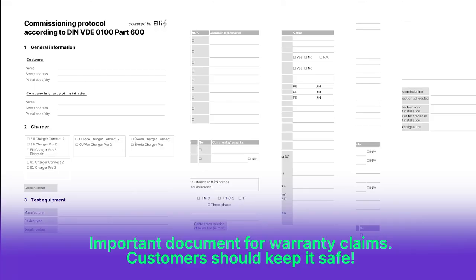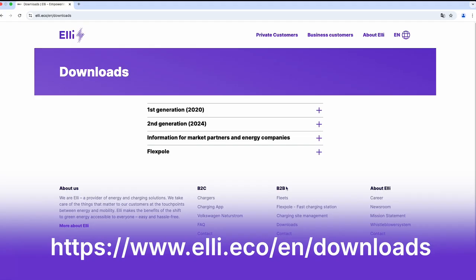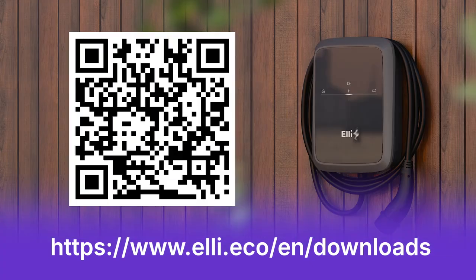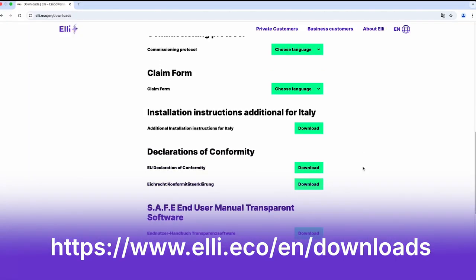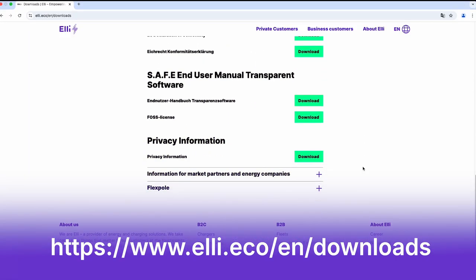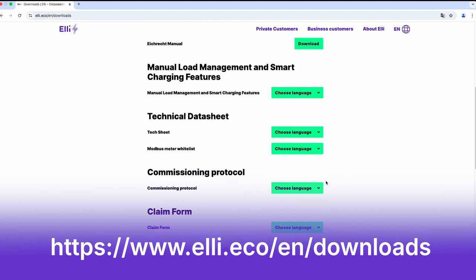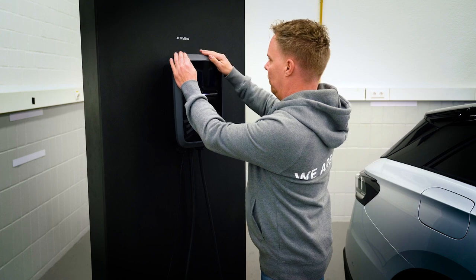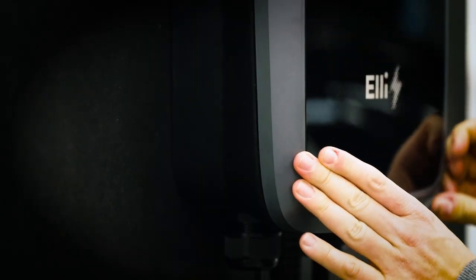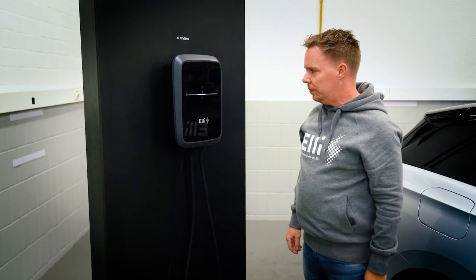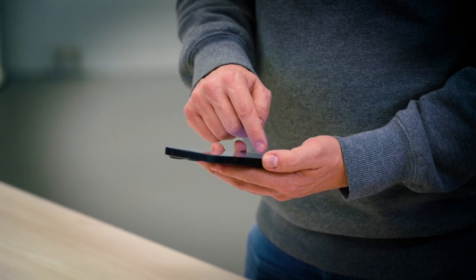After installation, a commissioning protocol must be completed and given to the customer. The protocol can be found in the download area of the Elli homepage or via the displayed QR code. Make sure that both the installer and the customer sign the protocol. In the download area, you will also find additional documents such as user manuals and datasheets in various languages. Once you have successfully tested the charging function, you can click the decorative frame onto the unit and make any further settings via the Wallbox configuration or the app.